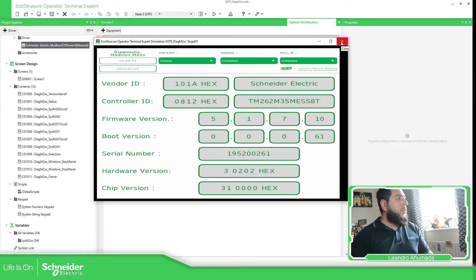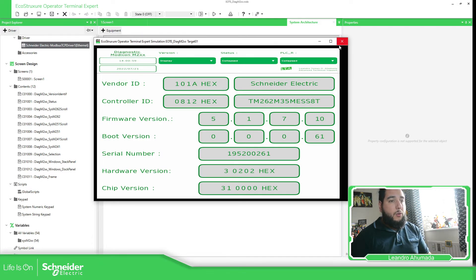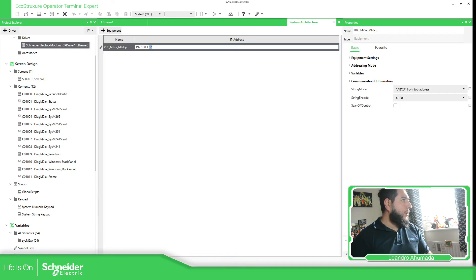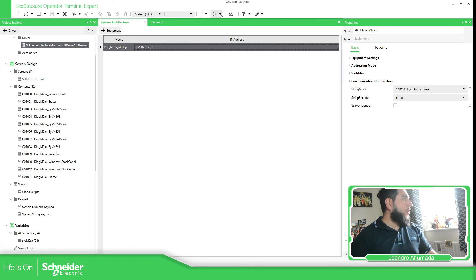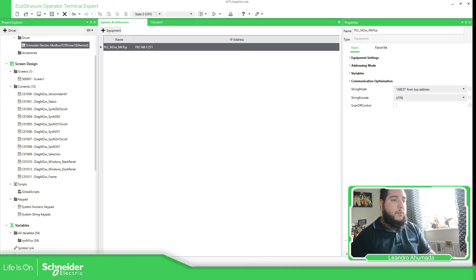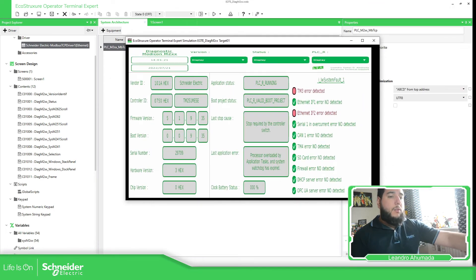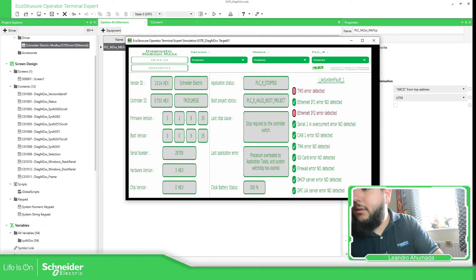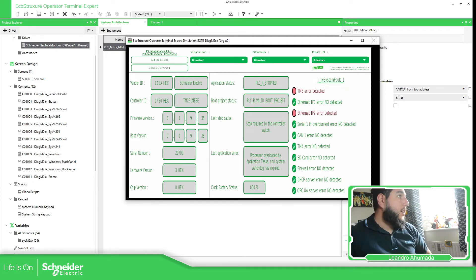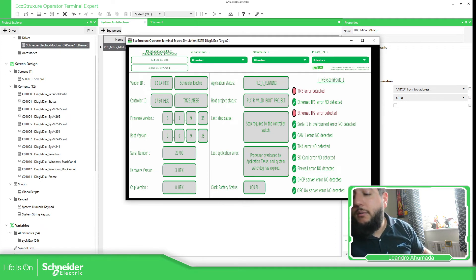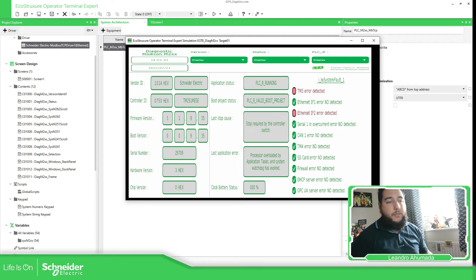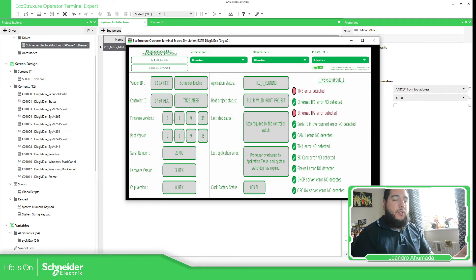This is one way to do it. Now I have the M251 in the same network. So instead of creating another HMI for this, I just changed the IP address. I'm going to simulate this now. Instead of seeing the M262, I should be able to see the M251. Now let me put this in a stop. You can see the PLC that I have on the bench is in a stop, and you can see the whole application is valid — stopped required by the controller switch. So if I put it in run, the PLC is running again. You saw the different application status over there.